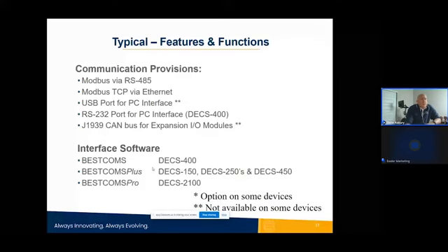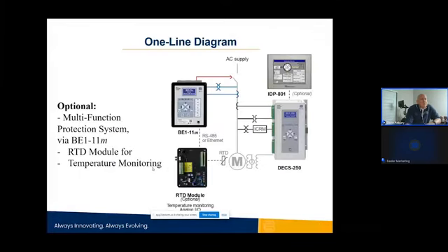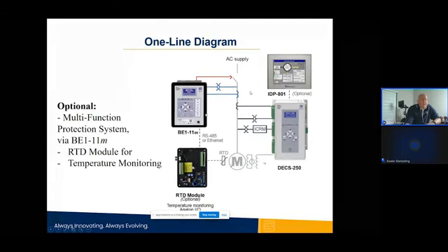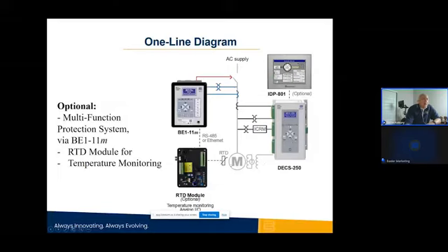Here's a one-line diagram of a typical DECS-250 working into a brushless excited motor. You do have an optional BE1-11M, that's our motor protection relay right now, with an RTD module. So we could set up a complete system that includes protection, controls, remote display. So we have a lot of different options. Like I said, this is optional.